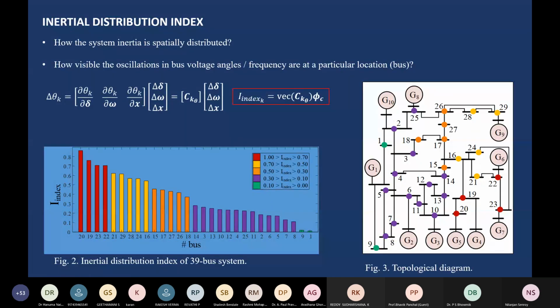The inertial index is an indicator of how the total system inertia is spatially distributed across the system. This kind of spatial distribution tells us that if you have a bus where a large inertia is present, that bus is the center of inertia of the system. So for instance, in this particular system, bus number 1 and 9 are the center of inertia. So here, if you have a fluctuation, if you have some hammering going on at bus number 9 or bus number 1, the system would not even oscillate. There would be no impact on the system.